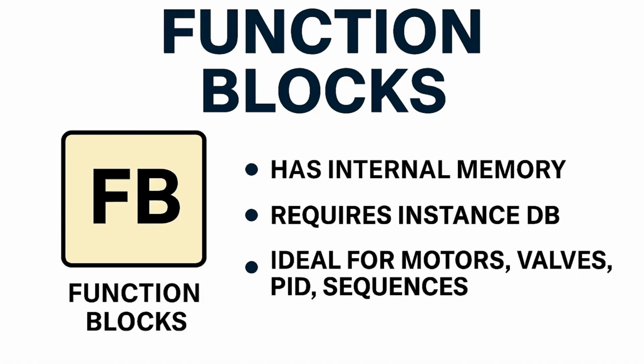Function blocks, or FBs, are similar to FCs but with one major difference: they have memory. Each FB requires an instance data block to store its internal states. Use FBs for equipment modules like motors, valves, PID loops, or anything that needs to remember values between cycles.